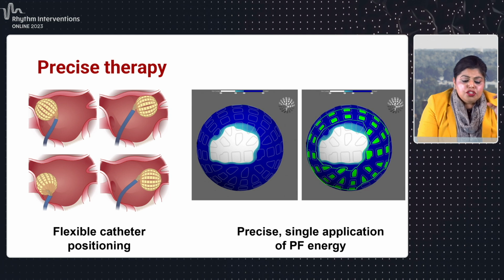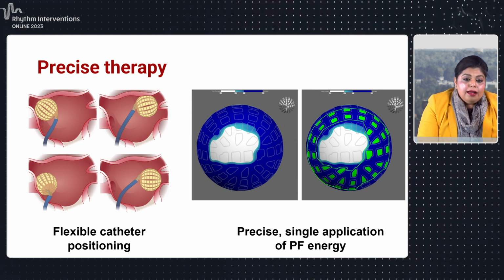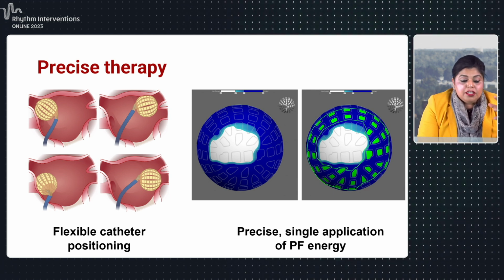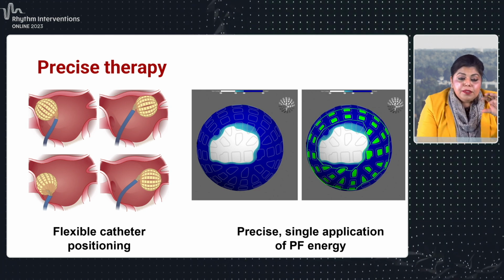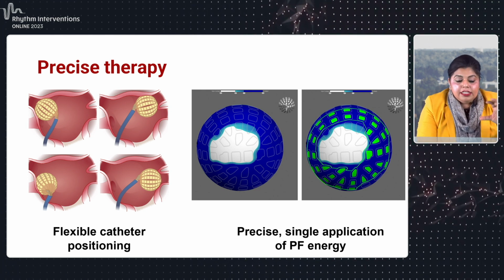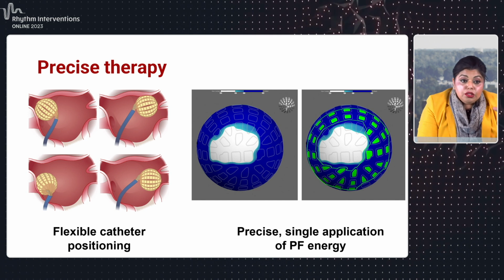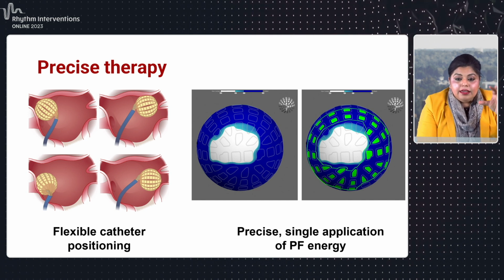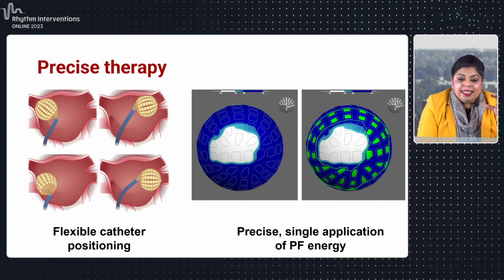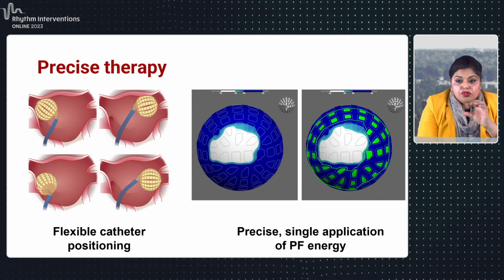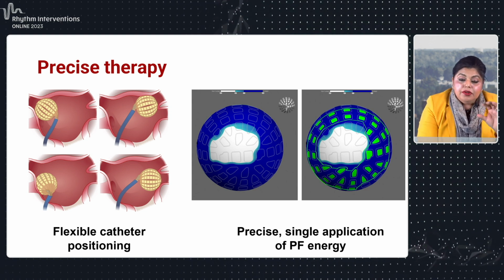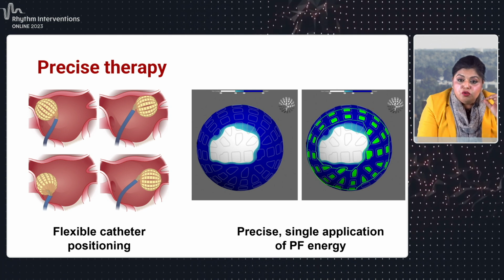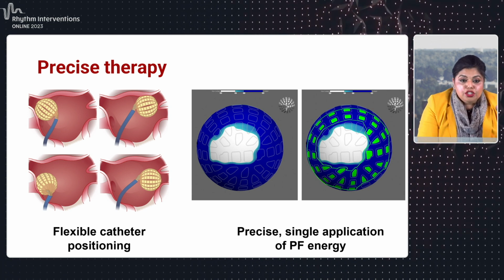And regarding just delivering the therapy, the catheter is very flexible. The sheath has bidirectional deflection. So you can actually position the catheter in different configurations along the pulmonary veins and have a very precise single application of pulse field energy by selecting those electrodes. So the green highlighted areas are the electrodes that are selected for those precise applications of the PF energy.